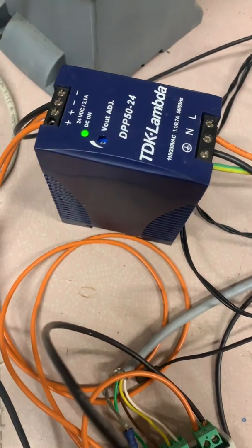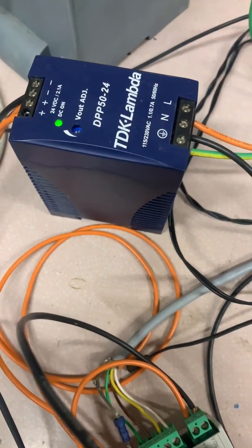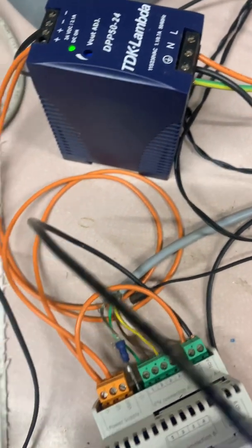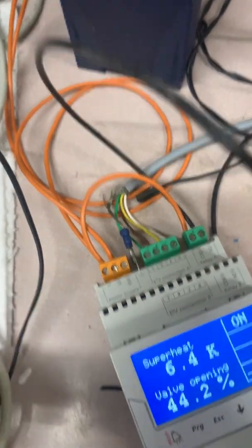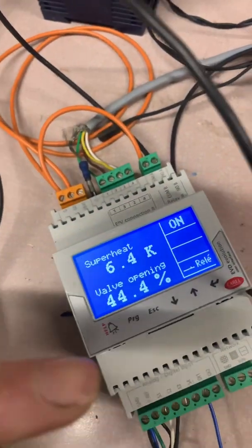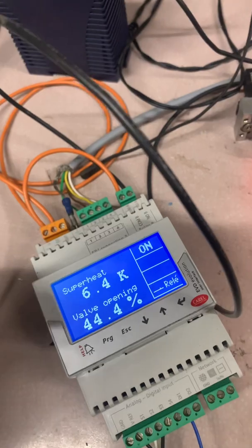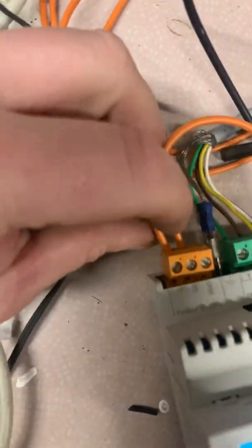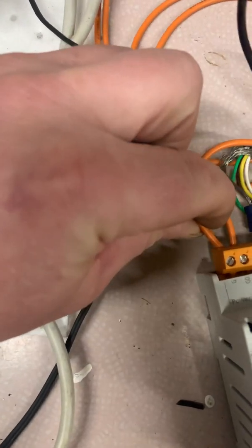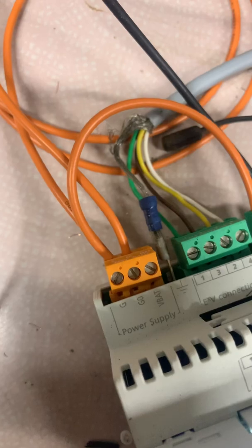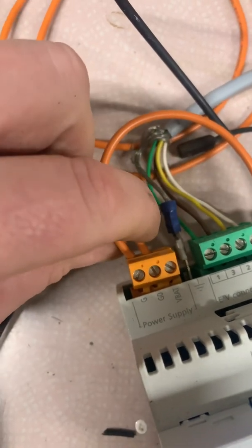Right then, today I've got a 24 volt DC supply. You can use a 24 volt AC supply. You've got to choose in the settings what you do, right? I've set it to number one, which is a DC supply. Positive is on G and negative on G0.